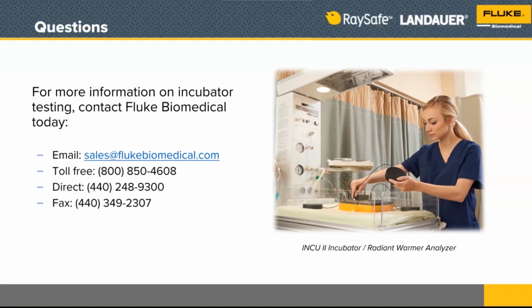Outside the United States, how often for electrical safety is at least once per year. Some manufacturers want electrical safety done every single time, and their field engineers are supposed to do it every single time if they follow the service manual test procedure. So that's kind of our answer. It depends on where you are in the world how often you do it, but generally at least once per year. Can you talk a little bit more about the warm-up time and how you test that?